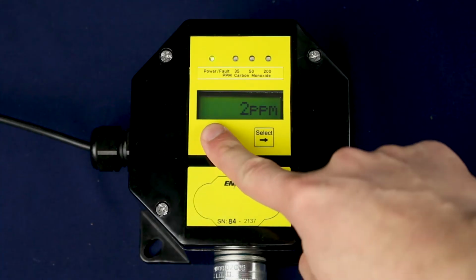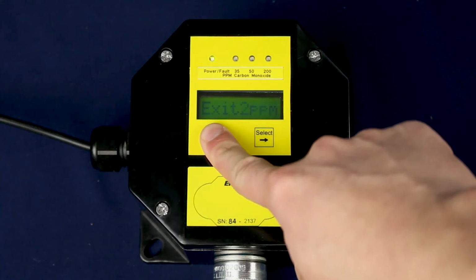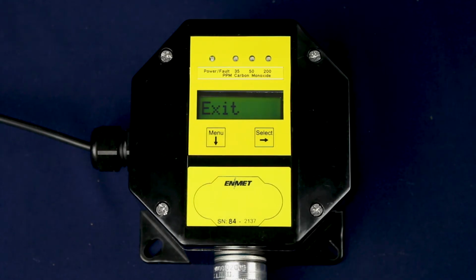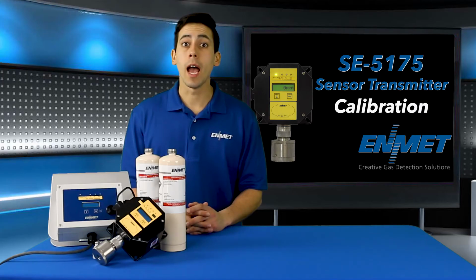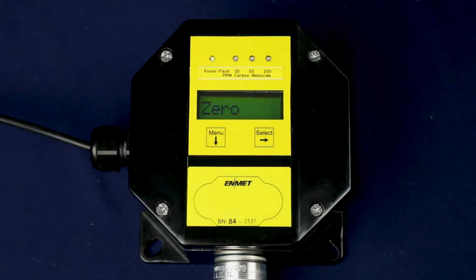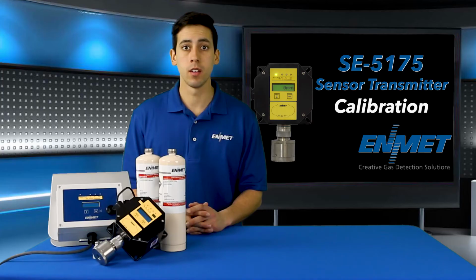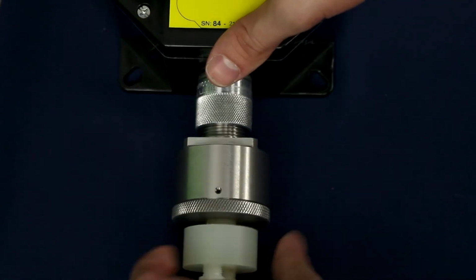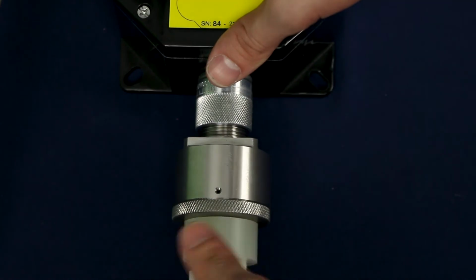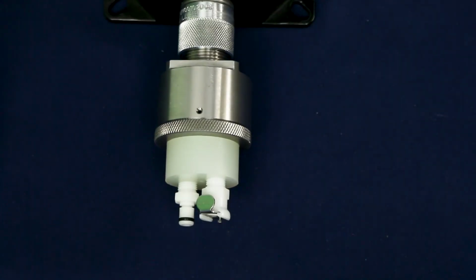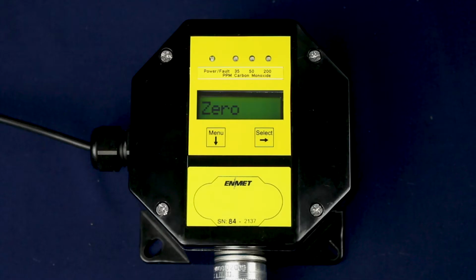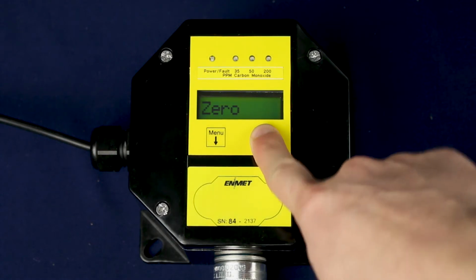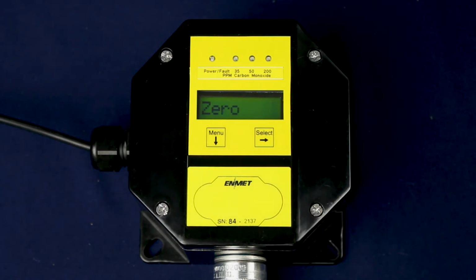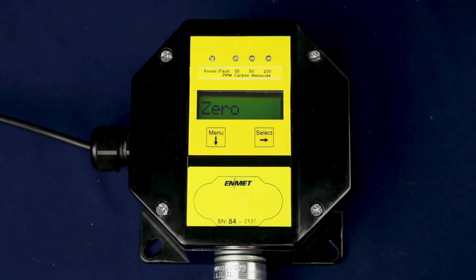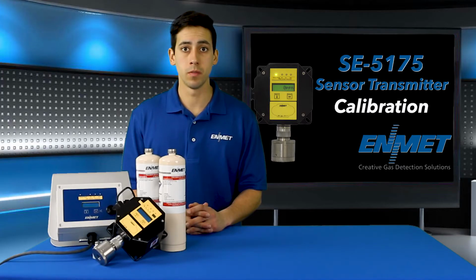Enter the maintenance menu by pressing and holding the menu button for 2 to 4 seconds until Exit appears on the display. After entering the maintenance menu, press the menu button until the zero menu option is displayed. Install the calibration adapter to the sensor head and connect the zero gas cylinder to the adapter. Press the select button to start the zero calibration. The display will alternate between 0 and PV. PV stands for present value.